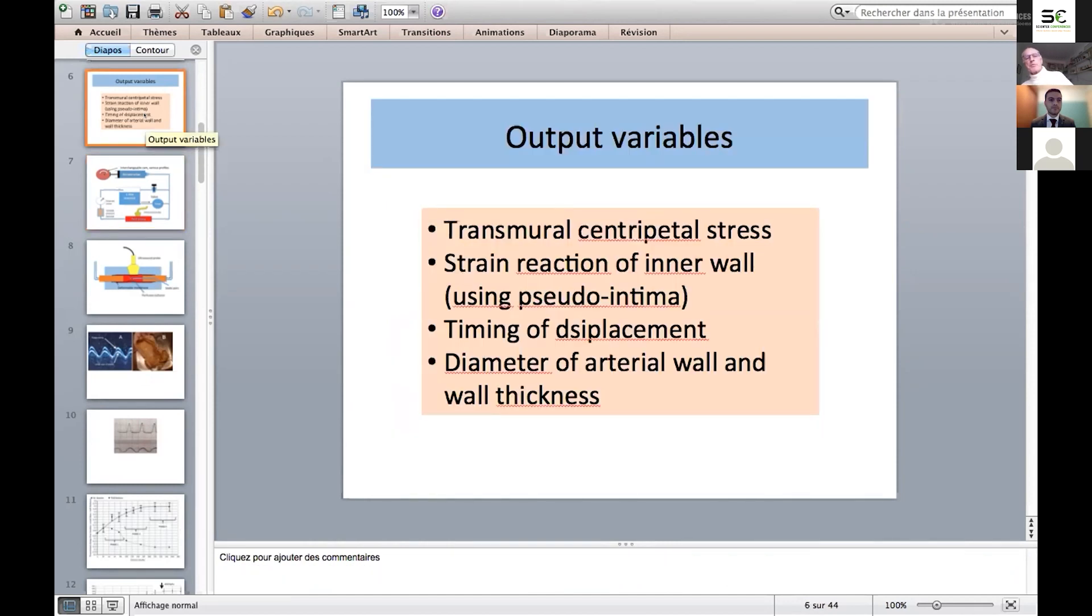The profile of that cam can be changed to change the nature of the pulse pressure wave. And the output variables, the things we can measure, are the centripetal stress across the inner surface of the arterial wall, the strain reaction of the inner wall using a deformable latex pseudo-intima, and the timing of the displacement and the diameter of the arterial wall in its response to changes in arterial pressure.